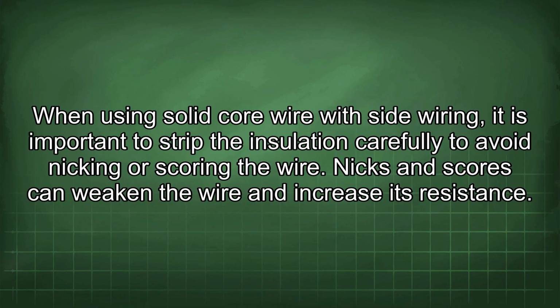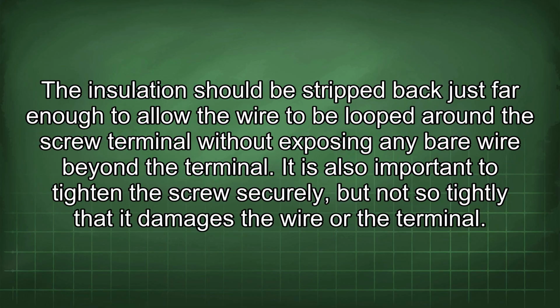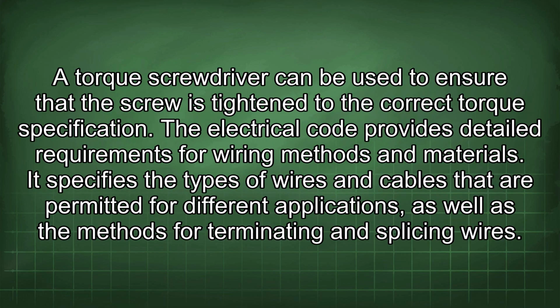When using solid core wire with side wiring, it is important to strip the insulation carefully to avoid nicking or scoring the wire. Nicks and scores can weaken the wire and increase its resistance. The insulation should be stripped back just far enough to allow the wire to be looped around the screw terminal without exposing any bare wire beyond the terminal. It is also important to tighten the screw securely, but not so tightly that it damages the wire or the terminal. A torque screwdriver can be used to ensure that the screw is tightened to the correct torque specification.